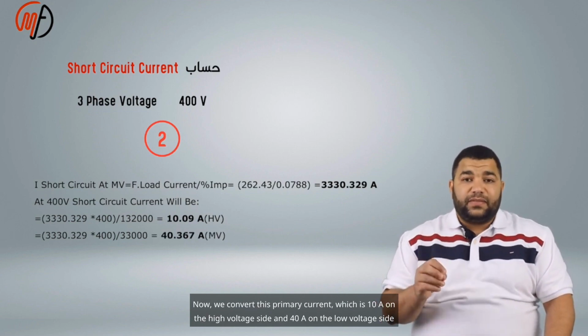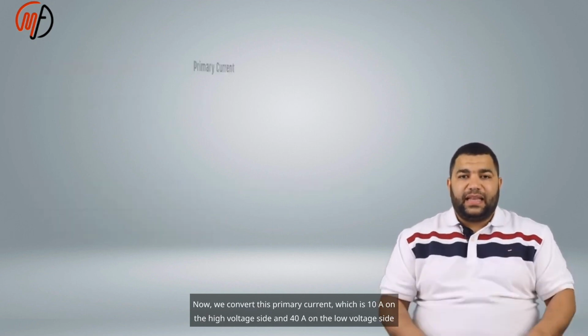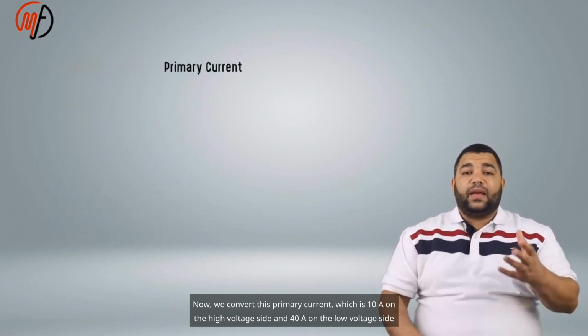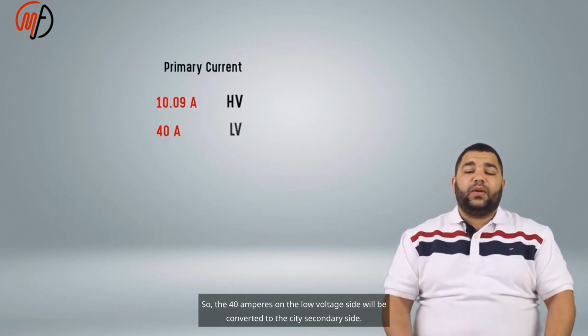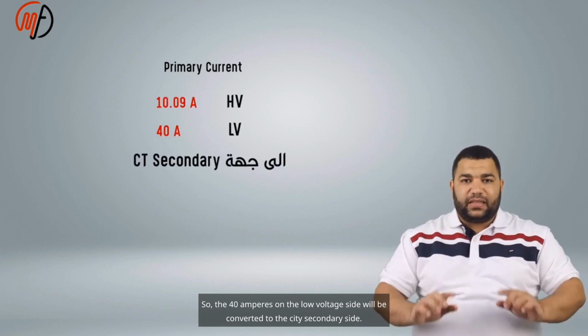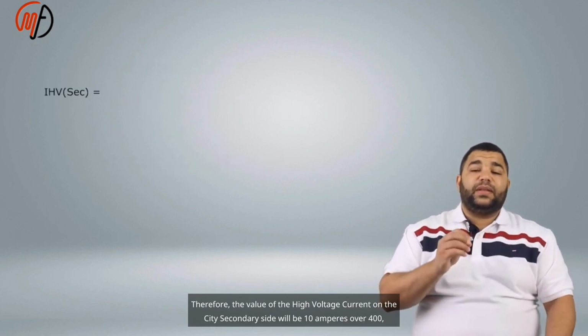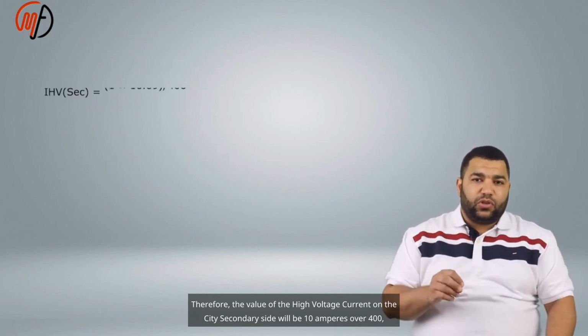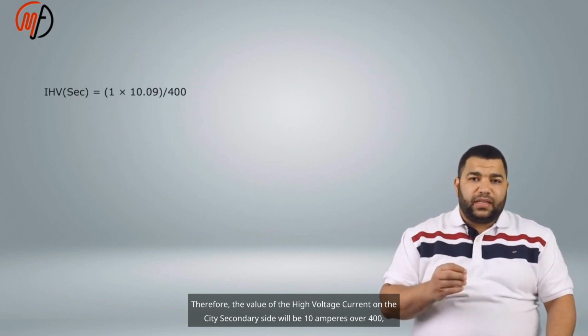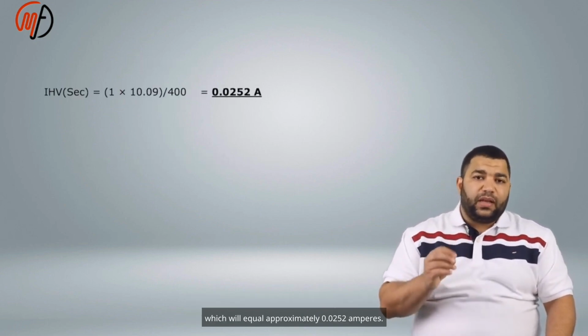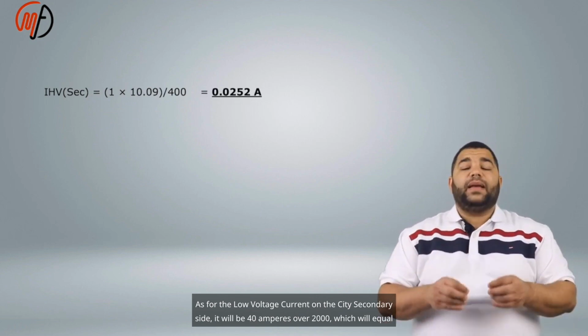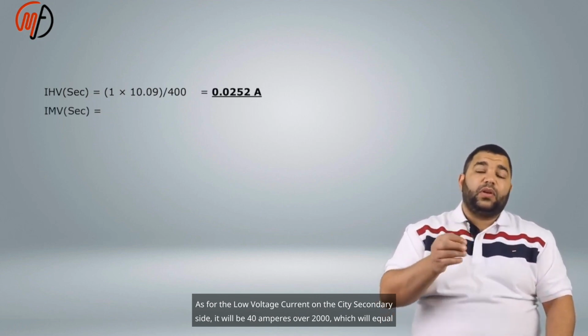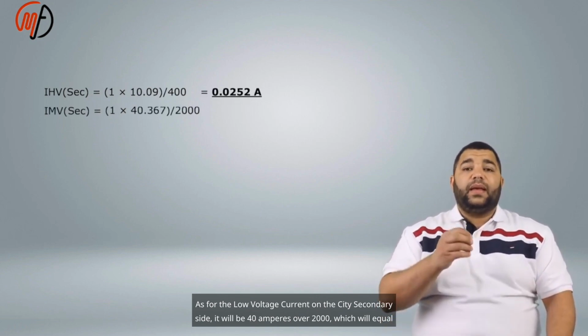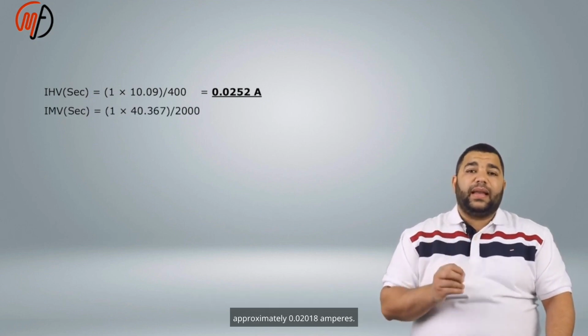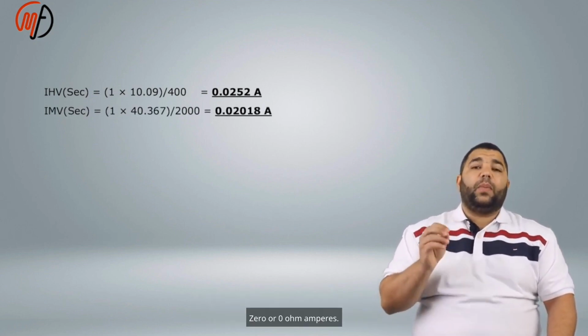Now we convert this primary current, which is 10A on the high voltage side and 40A on the low voltage side, to the CT secondary side. So the 40 amperes on the low voltage side will be converted to the CT secondary side. Therefore, the value of the high voltage current on the CT secondary side will be 10 amperes over 400, which will equal approximately 0.0252 amperes. As for the low voltage current on the CT secondary side, it will be 40 amperes over 2000, which will equal approximately 0.02018 amperes.